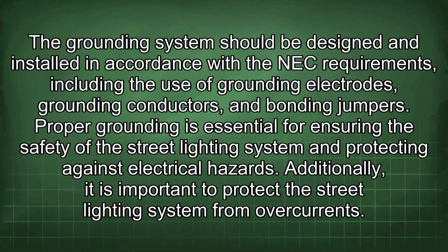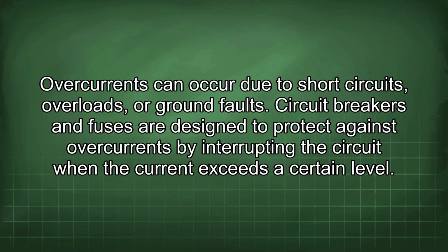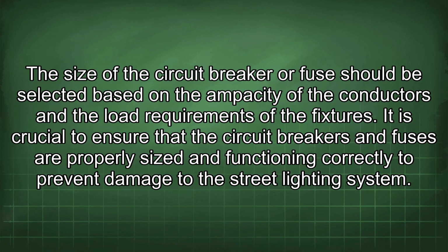Additionally, it is important to protect the street lighting system from overcurrents. Overcurrents can occur due to short circuits, overloads, or ground faults. Circuit breakers and fuses are designed to protect against overcurrents by interrupting the circuit when the current exceeds a certain level. The size of the circuit breaker or fuse should be selected based on the ampacity of the conductors and the load requirements of the fixtures. It is crucial to ensure that the circuit breakers and fuses are properly sized and functioning correctly to prevent damage to the street lighting system.